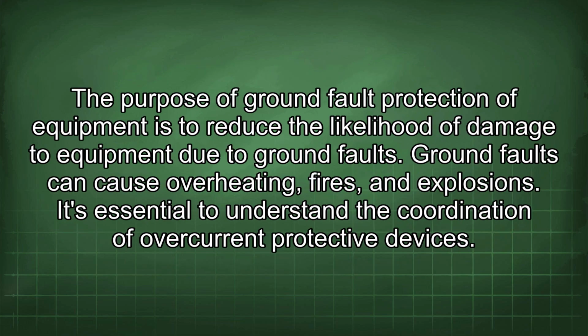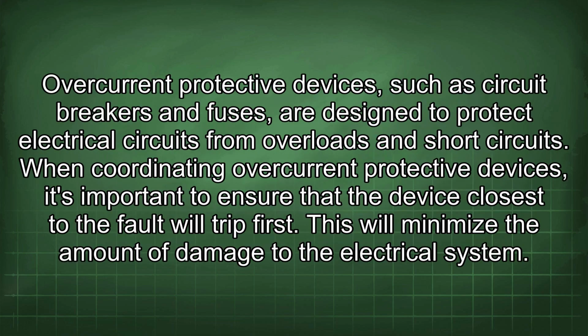The purpose of ground fault protection of equipment is to reduce the likelihood of damage to equipment due to ground faults. Ground faults can cause overheating, fires, and explosions. It is essential to understand the coordination of overcurrent protective devices. Overcurrent protective devices, such as circuit breakers and fuses, are designed to protect electrical circuits from overloads and short circuits.